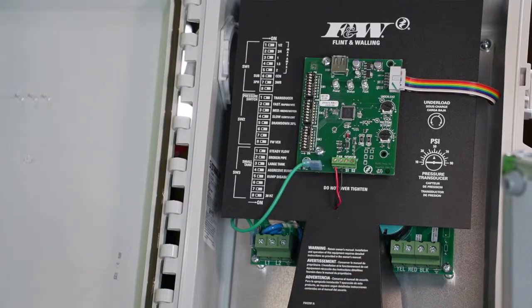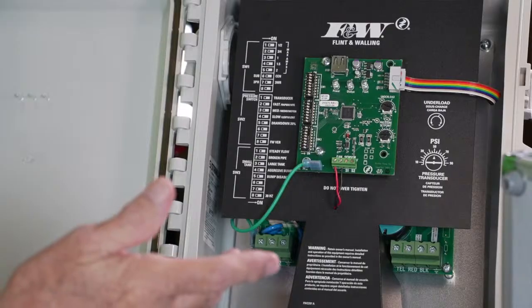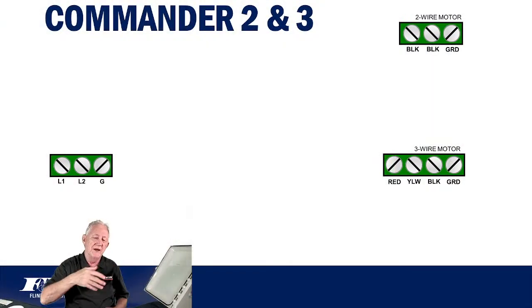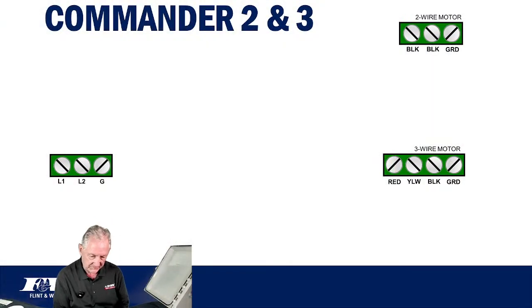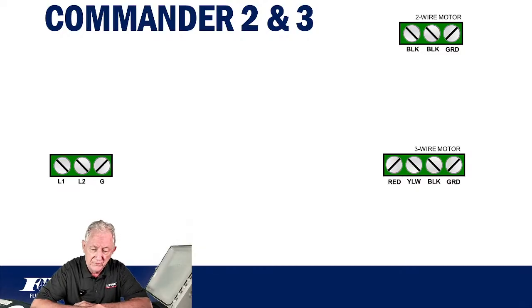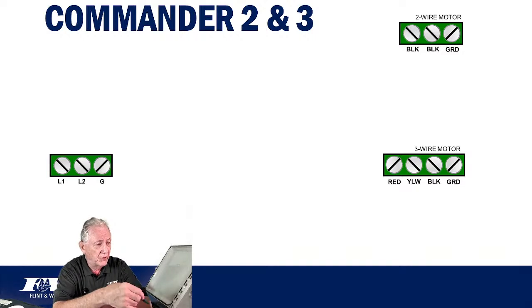Now, there are slight differences between the Commander 2 and the Commander 3. The Commander 2 is designed for 2-wire motors, and this will virtually run anybody's 2-wire motor. Whereas the Commander 3 is designed for 3-wire motors, so it's very, very easy to differentiate those two. Now, there are some subtle differences between these two drives, particularly on the inside here.